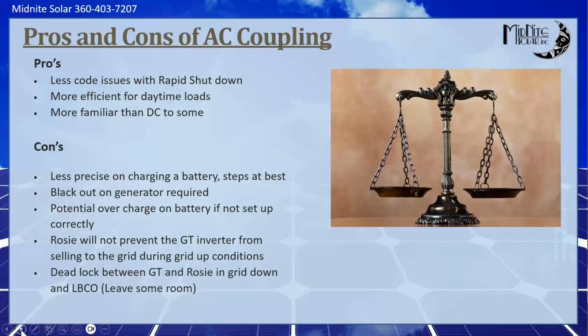So if the grid tie inverter is forcing 5 kilowatts down its throat, it has to put that 5 kilowatts somewhere. It can't regulate that. Like when it's charging from the grid, it can just change its voltage a little bit to drop the charge current, and all is good. But on the grid tie inverter, the only choice it has is to either frequency shift to throttle it, or it's just uncontrolled charge. So that's why it's important to verify after you program, in the functionality test.